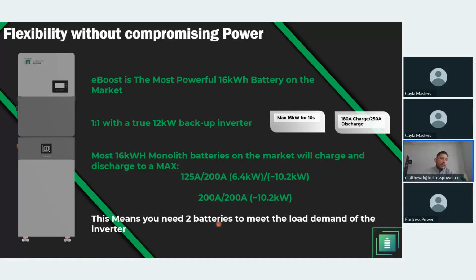Whereas with the eBoost, with one battery, or with one battery with the inverter stacked on top, you will meet those load demands. It is able to charge at 180 amps DC and discharge at 250 amps DC continuous, max continuous, with a peak surge of 16 kilowatts for 10 seconds. So it's a very, very powerful battery for your continuous usage without any glitch or issues.